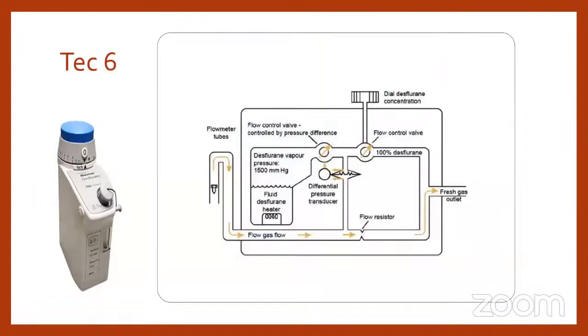Coming to the next generation of vaporizers developed by GE, it is the Tec 6 vaporizer. It is basically agent specific, only for desflurane, because desflurane has the lowest boiling point of the lot. The boiling point is 22 degrees centigrade, which is way less than our room temperature. So if we keep desflurane even at room temperature, the evaporation rate will be very high, and the amount of vapor produced will be very high. The amount that mixes with the fresh gas will be very high, and the amount delivered to the patient is also very high. To avoid this high flow, high delivery system, they have developed this special vaporizer exclusively for desflurane. It basically has a heater, a coil heater, and it also requires a power supply.